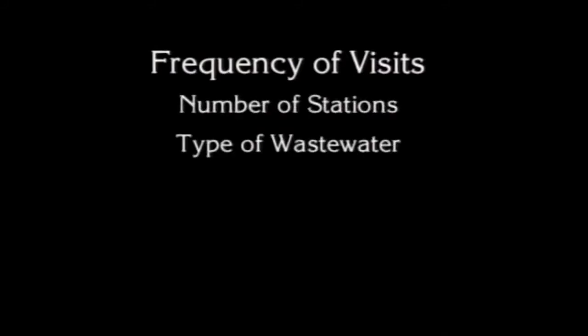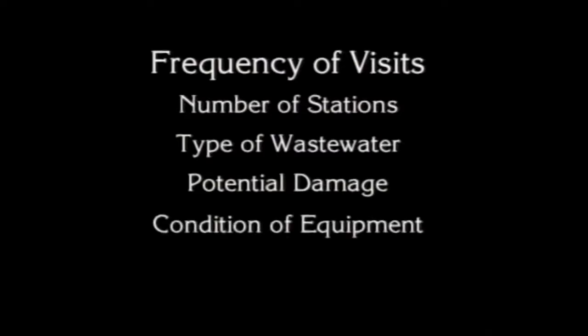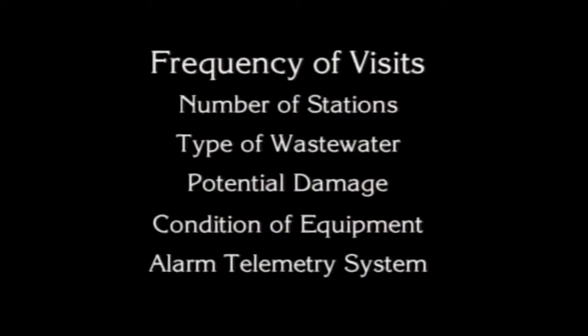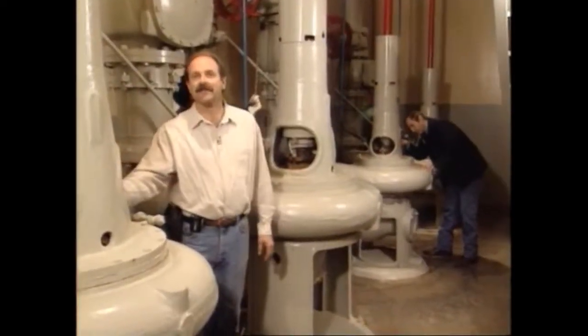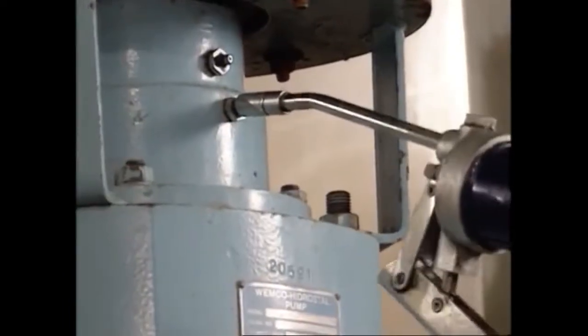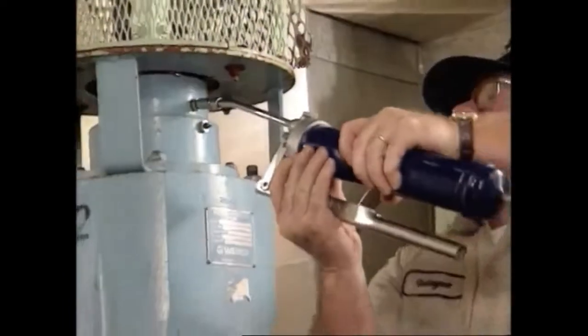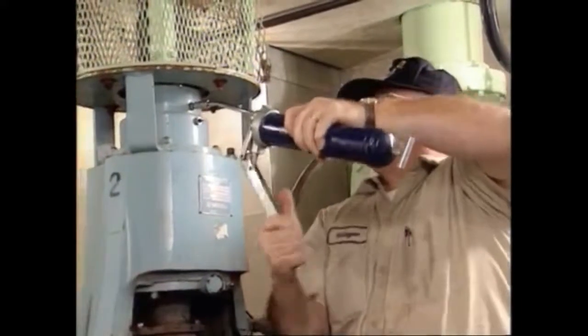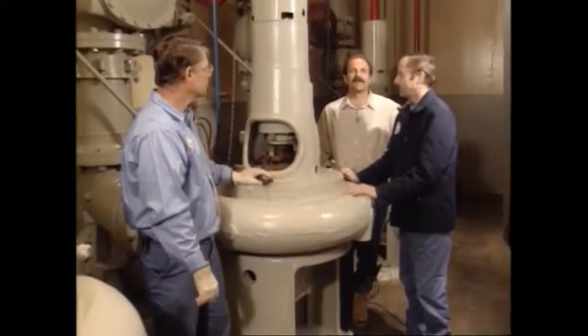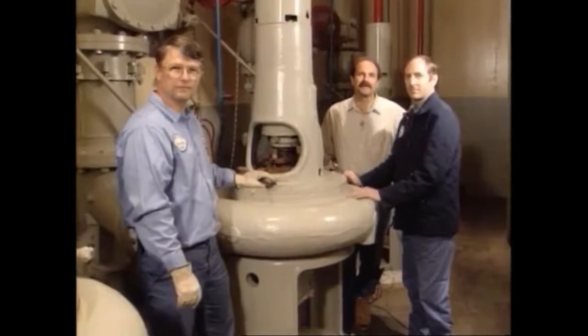Because there are many factors involved, it would be impossible to suggest how often to visit and inspect your lift stations. Frequency of lift station visits depends on the number of stations in the community, the type of wastewater being conveyed, the potential damage resulting from flooding the station, the condition of equipment, and the alarm telemetry system. The design of the facility and the equipment installed are also factors. How well you follow your preventative maintenance program will also determine the need and frequency of visits. Of course, the number of available employees also plays a part in the number of visits to the facility.